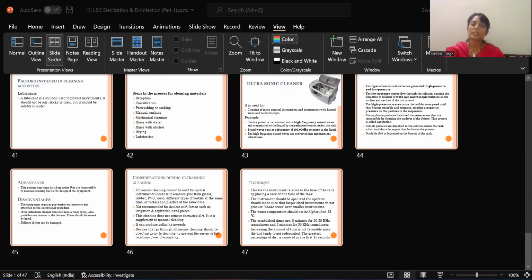Now, the limitations for these chemical sterilants are chiefly that they reliably produce sterility only if the cleaning treatment and proper guidelines incorporating the concentration, contact time, temperature, and pH of the agent are incorporated into the process. Secondly, the devices cannot be wrapped during the processing in the chemical sterilant, as is necessary to maintain sterility after processing and during storage. Now, after exposure to the liquid chemical sterilant, devices will require rinsing with water that is usually not sterile.